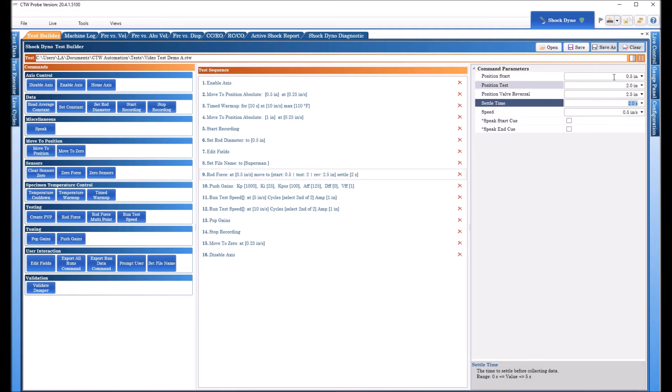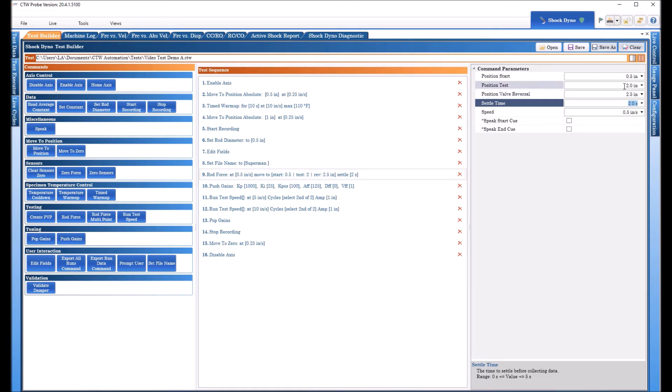And we can say we're going to test at two inches, position reversal we're going to go to 2.5 and pause for two seconds. So it's going to start at a half and it's going to move to two inches and it's going to pause for two seconds and take a force reading then it's going to move up to two and a half inches then come back to two inches and pause again for two seconds take another force reading.